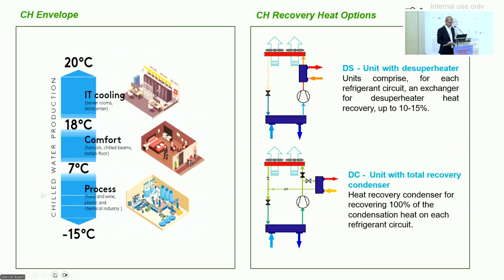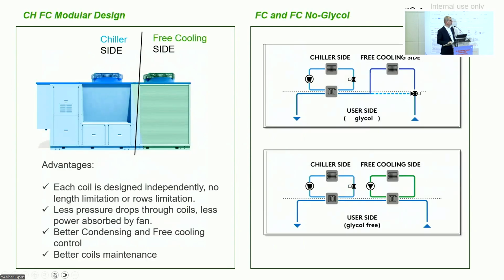We have cooling-only solutions with capability to produce water down to -15, and the ability to be completed with partial or total heat recovery solutions. Free cooling versions where we use a solution with separate coils, not condenser and free cooling coils facing one the other, but separate, so that the free cooling fans can be run at maximum speed to optimize the free cooling performance whenever possible, and we can integrate free cooling non-glycol executions.